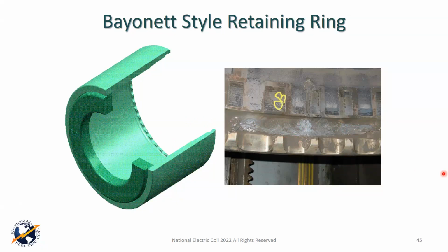There's a question here about smaller air-cooled machines. Now GE does not pull the rotor as often, only robotic inspection. Well, I don't know if I'm going to hit on robotic inspection a little bit later or not. We're going to be running out of time eventually, but I will tell you this. When you say smaller air-cooled, the robotic inspection is limited by three things: thickness of the robot, thickness of the air gap, and the relationship between the step iron and the nose of the retaining ring.